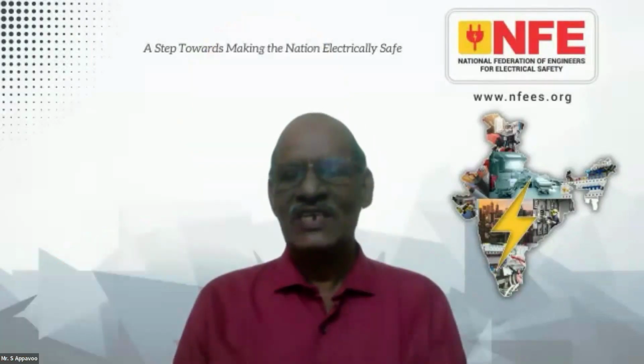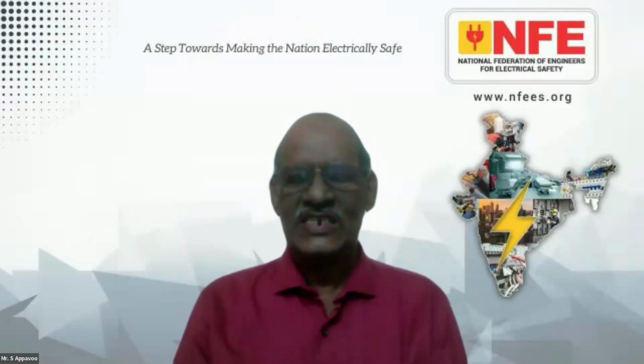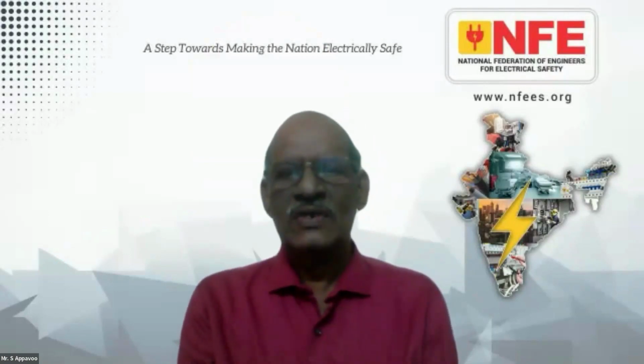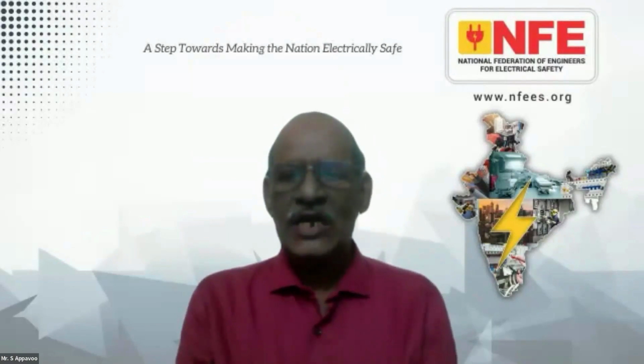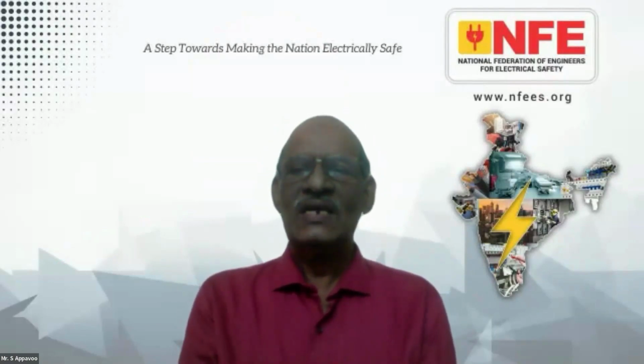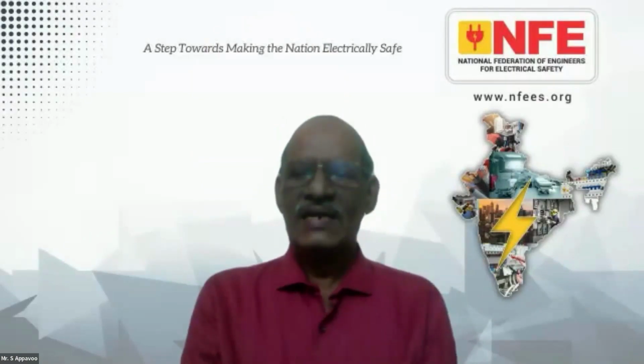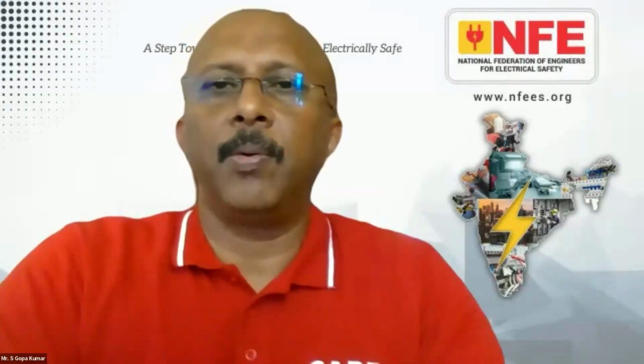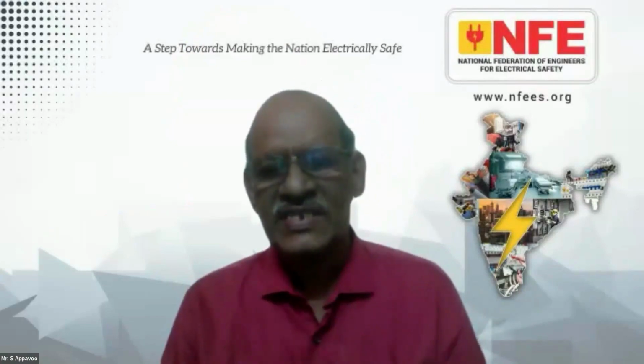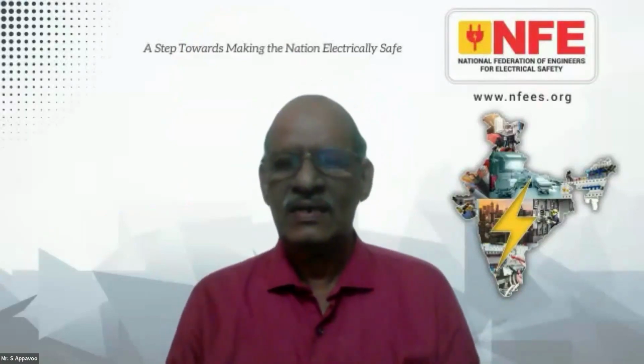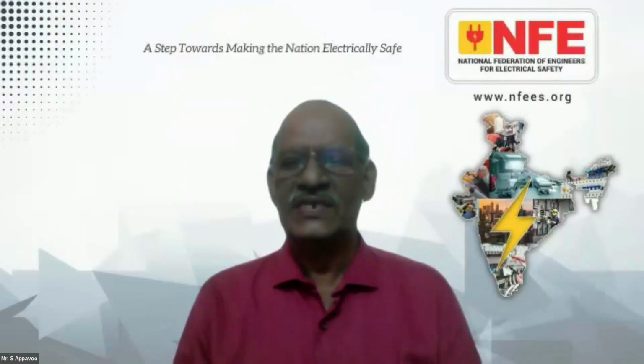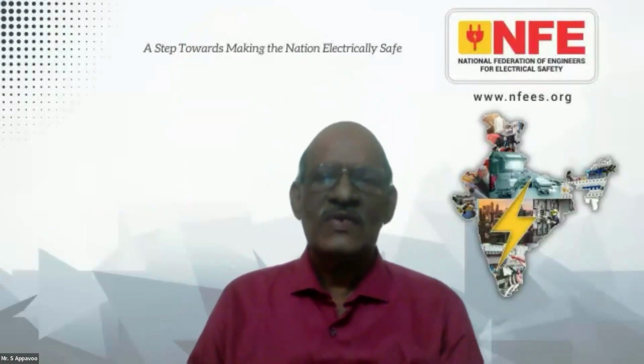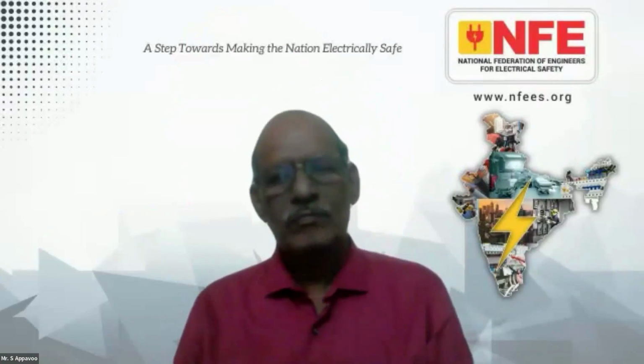Nothing happened. Something like LT insulation and ST insulation. In 230 volt, you have to ensure. There are devices which can sense the availability of high voltage while you bring your earth rod nearest to the live conductor. If it is live, then you will not discharge. You have to discharge the accumulated static and induced charges alone, not live charges, not live discharging. That's the intent. The size is not important here.